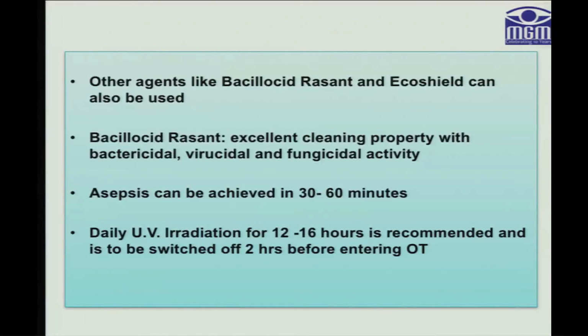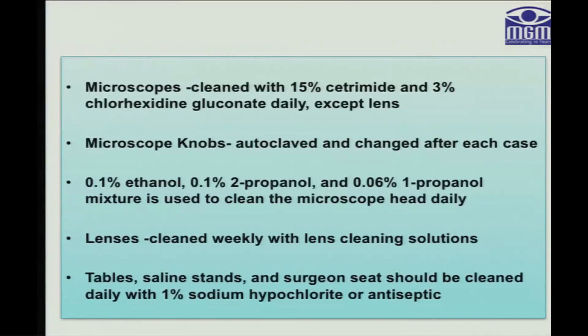And also one important thing is the UV radiation. Daily UV radiation of 12 to 16 hours is recommended, and it has to be switched off 2 hours before entering the OT. Microscopes are cleaned with 15% cetrimide and 3% chlorhexidine gluconate daily, except the lens. Microscope knobs are autoclaved and changed after each case. Lenses are cleaned weekly with lens cleaning solutions.